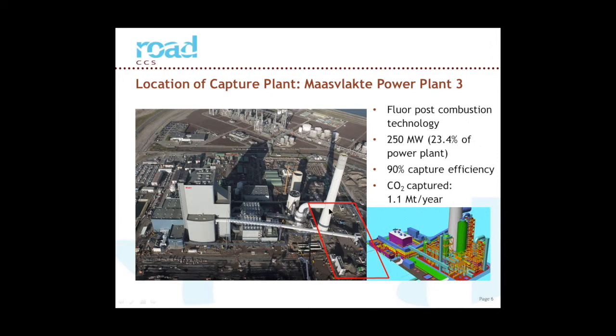So in terms of the water balance, the important thing to be aware of is that the flue gas is saturated at about 50 degrees as it goes into the stack, and that's a significant water loss. And the FGD takes about 120 tonnes an hour of water to quench the flue gas, which is, it's not drinking water, it's sourced from a nearby freshwater lake.